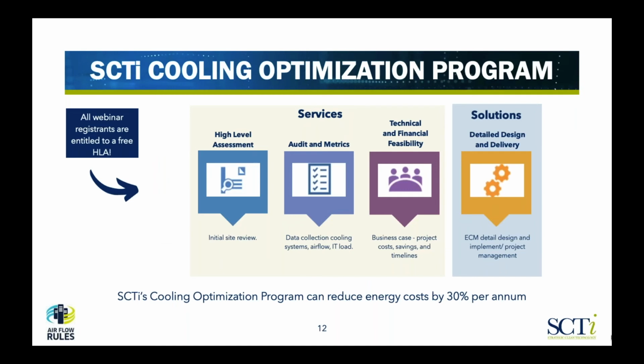The program is effective in optimizing cooling and providing positive results for the client for a few reasons. First, we do extensive data collection to understand how the data center works. We do not come in with a preconceived solution in our mind. We do energy metering pre and post project, so we can create a picture of the cooling energy consumption in the site. And we provide the client with projected energy savings and energy incentives as part of the business case.